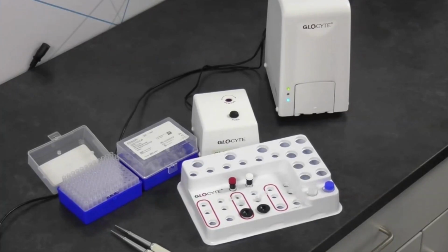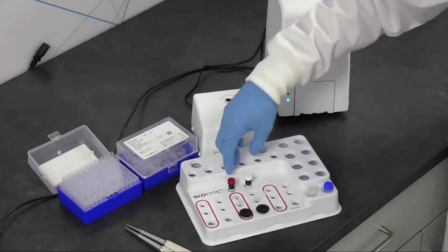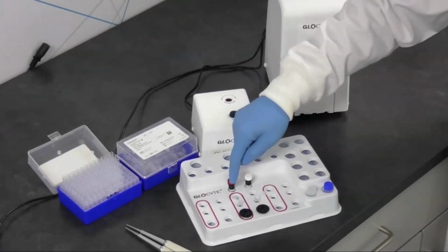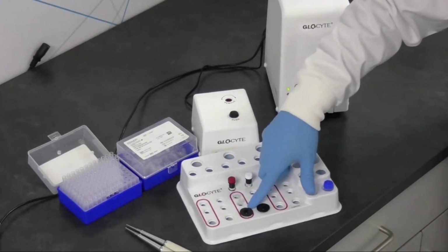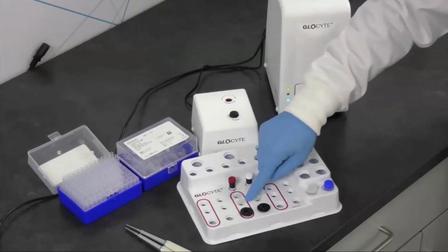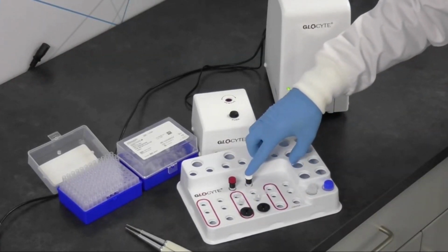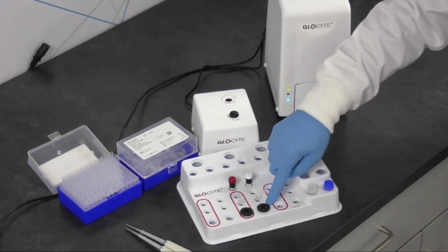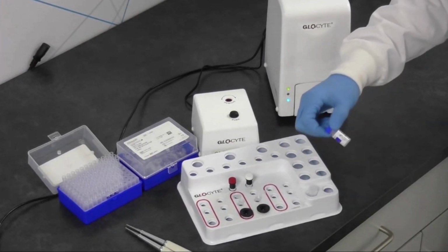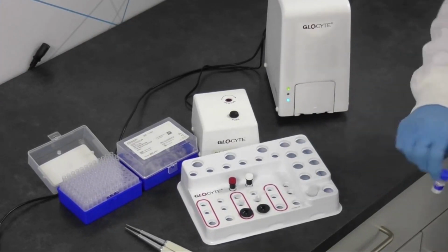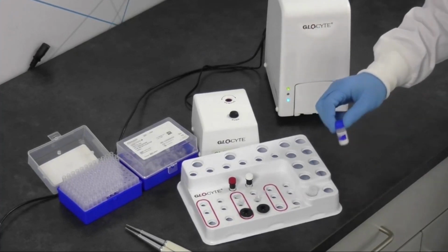So what you're seeing on the screen here is your 30 microliter pipettes, your sample tray, which has a space for your red blood cell reagent, which is going to sit in front of the red oval here, which contains this little black thing, which is your actual test cartridge, and your sample cup here. And then over here, where there's no red circle next to it, you're going to have your white blood cell reagent, your sample cup, and your test cartridge here. Over here is a place for your standards, for your controls. We're actually going to use one of our standards as our patient sample today, since we're running a demo. And I don't have anyone's CSF sitting around, for good reason, because we're here at our home site in Norwood.